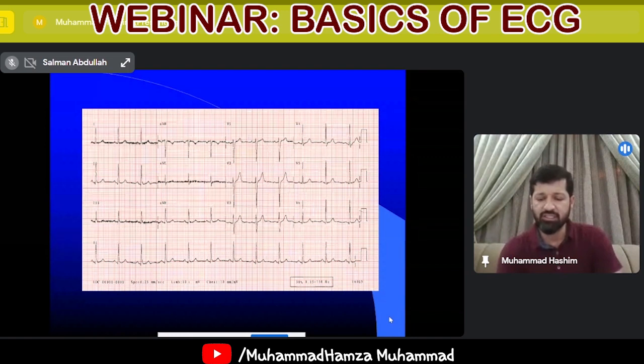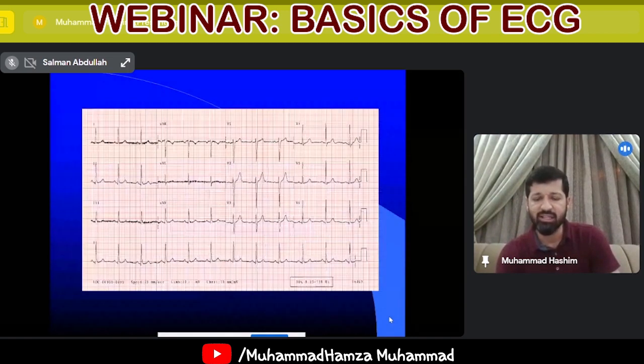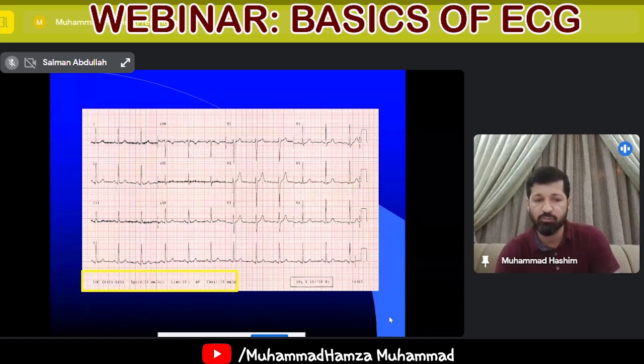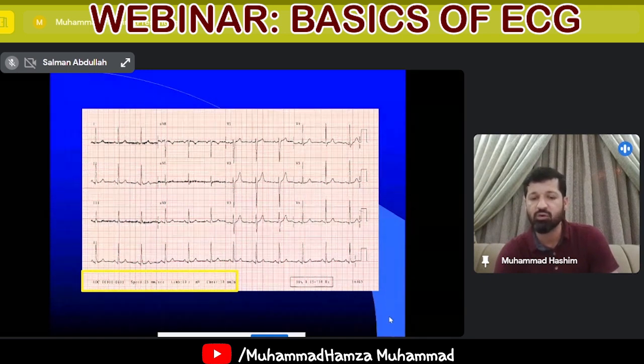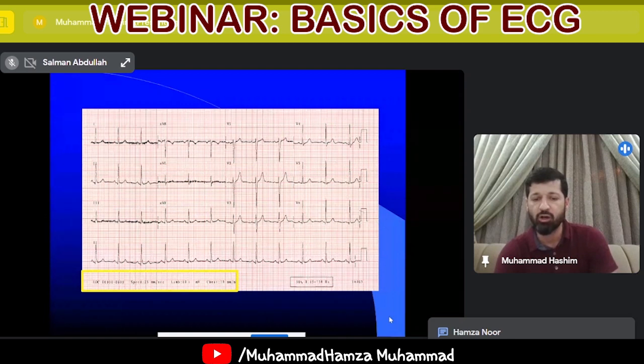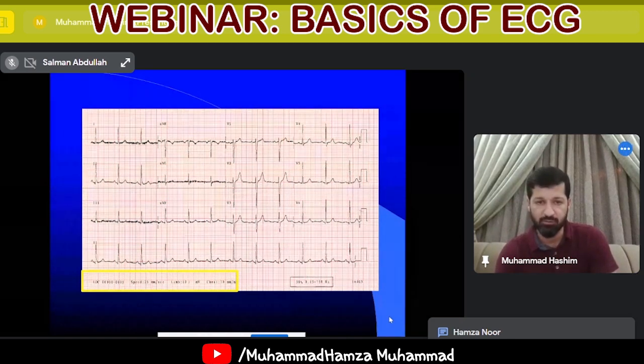Now, why is that ECG not complete? Because it doesn't have the standardization in the end. The normal standardization is that the speed of the ECG paper should be 25 mm per second, and the voltage should be 10 mm equal to 1 millivolt. It means that 1 second of electrical activity should be measured on 25 mm of the ECG strip. And when the heart produces 1 millivolt of electrical activity, that should be 10 mm on the ECG paper.